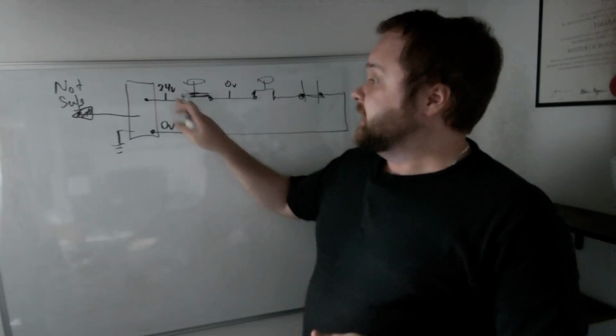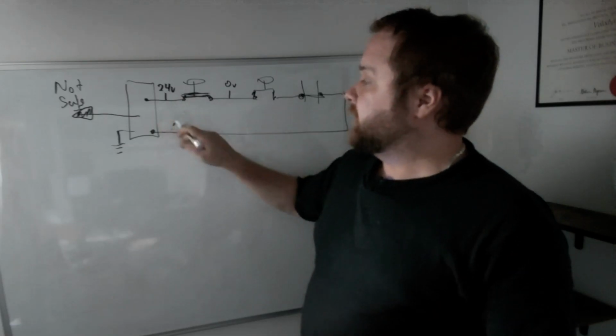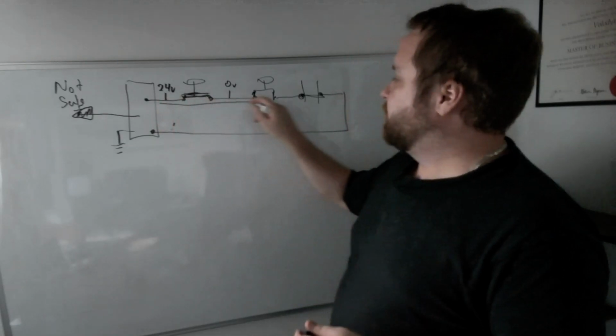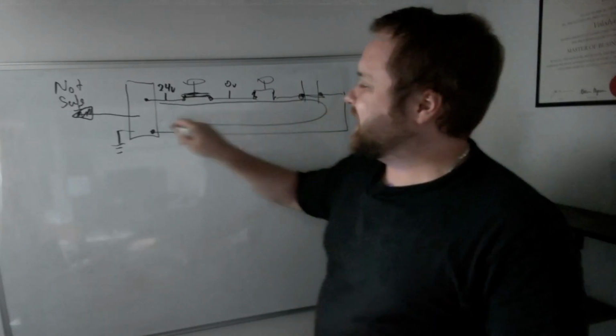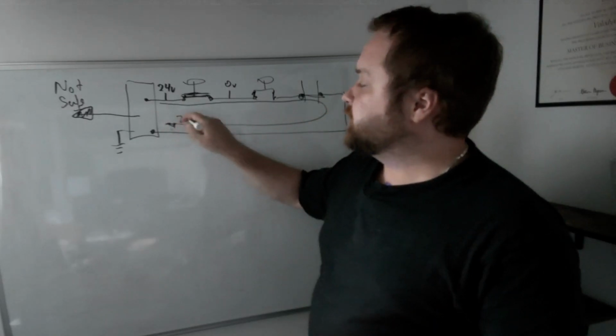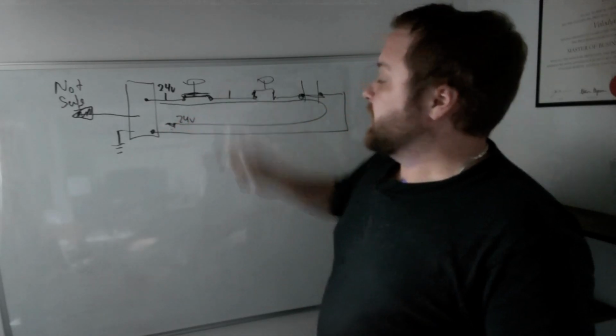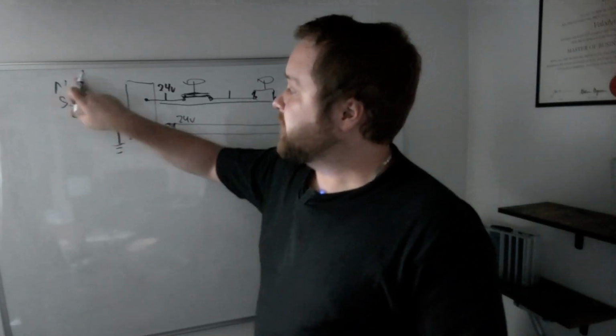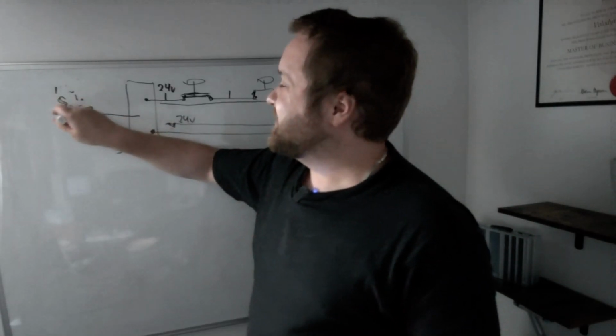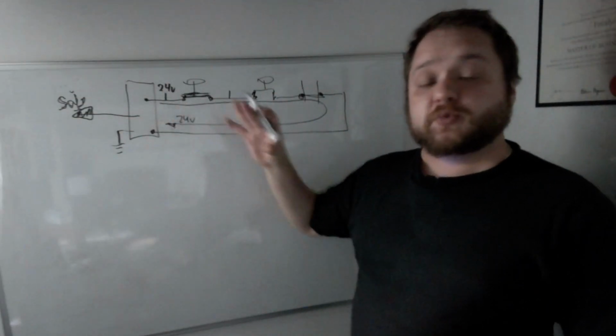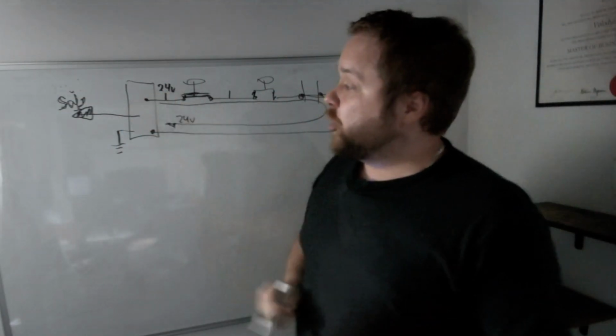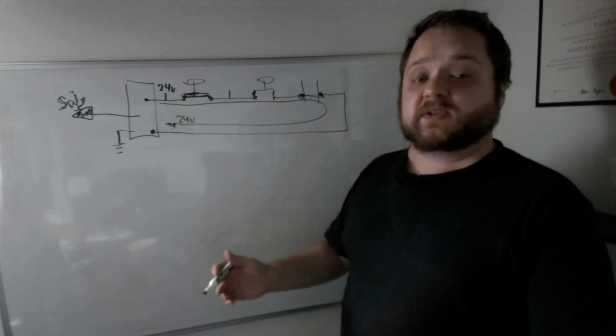curtain. But in this case, we now have a chain going through 24 volts, all the way back to the safety relay. So here we're now reading 24 volts. And basically, it's going to say that the application is indeed safe, and we can energize whatever equipment needs to be operated based on the state of this specific safety relay.